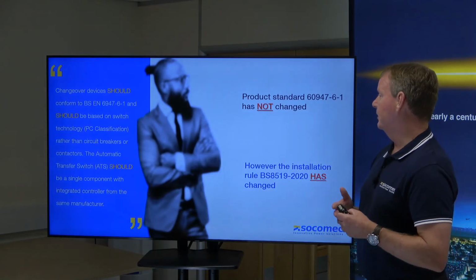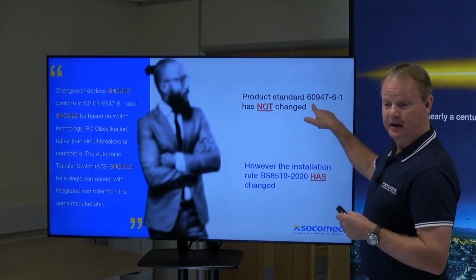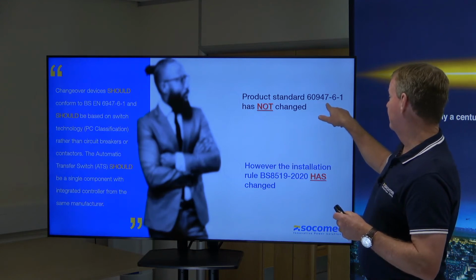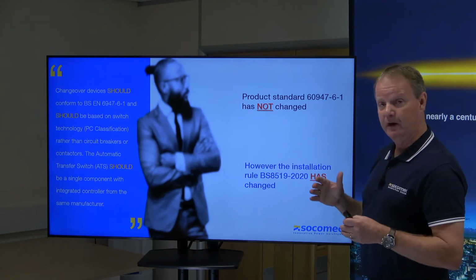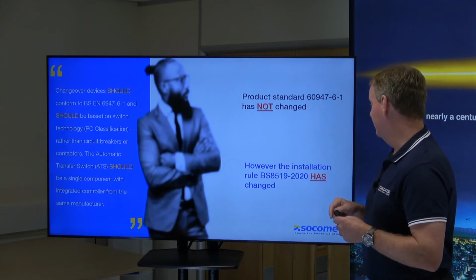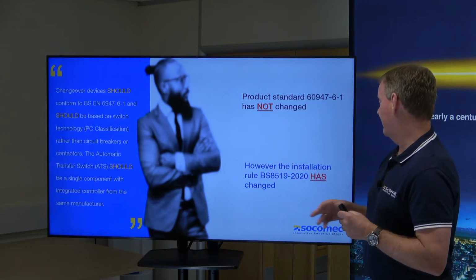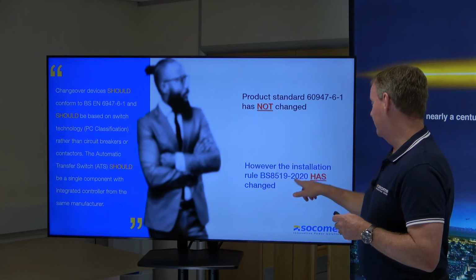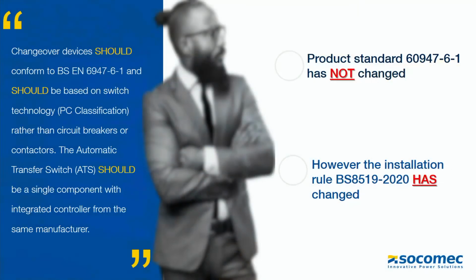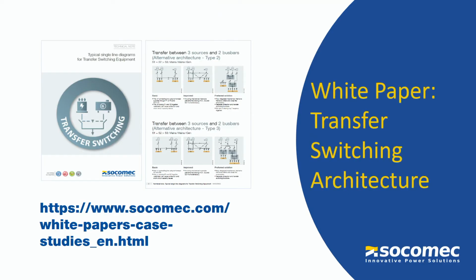So really, two main points to take away is that the product standard hasn't changed. 60947-6-1 is still current because it's a product standard. However, the installation rule or code of practice, BS 8519-2020, has changed. You can see here on the slide, if you're not sure or you need some more information, there's a web page there, socomec.com, white papers, where you can get some more information on transfer switching architecture.